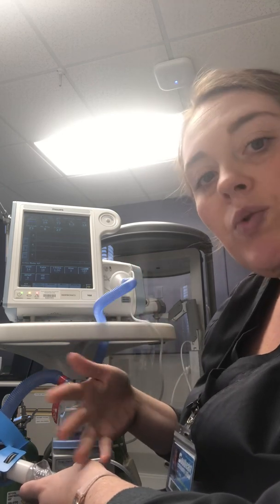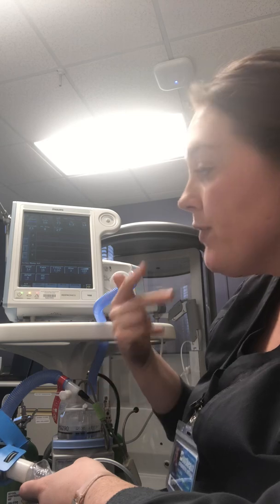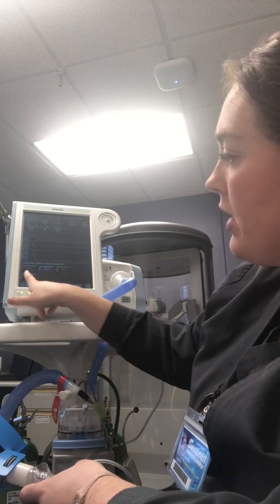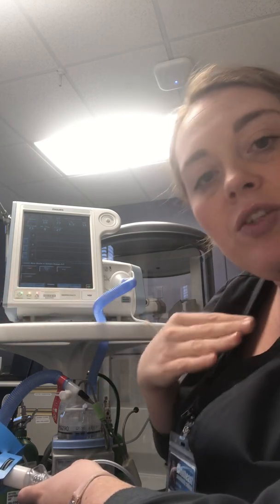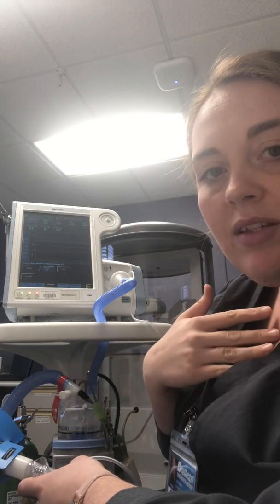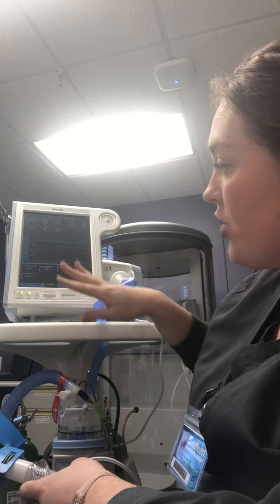This type of machine can also be a CPAP or an APRV machine. So to change that, you would just go to modes, and you can change to CPAP, which is just the one constant pressure versus the differential pressure that we see with Bipap. So that's how you would change that. And that is how you use the Bipap, the V60 Bipap.